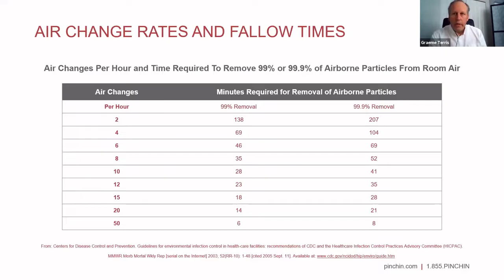However, the thing to think about when you're doing that is that you've got to make sure you're not creating more drafts. So positioning of the unit is quite important. I'm trying to get to a picture of one. This is part of section 44 of that document, but basically it's suggesting you should use an HVAC professional to check your air change rate on your existing system before you add anything additional. It may well be your existing system will provide a better air change rate than perhaps you think. But the other thing to think about is if you increase your air volume too much in your system, then you might start creating drafts, which goes back to what I was talking about earlier about drafts being an issue for carrying the virus.